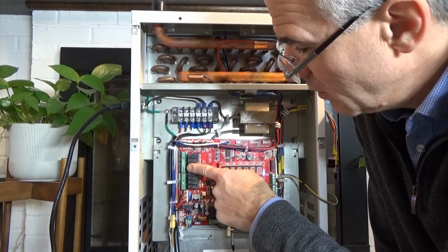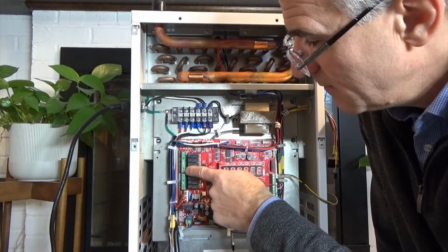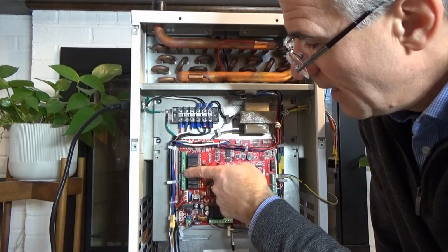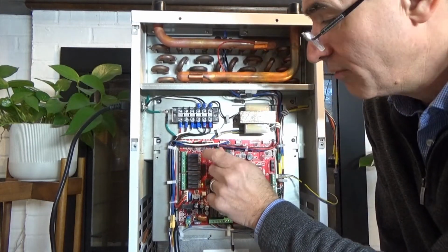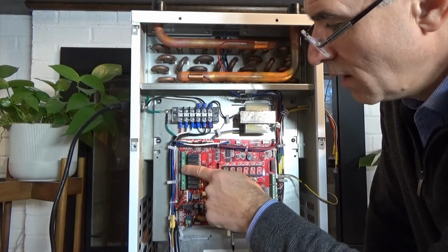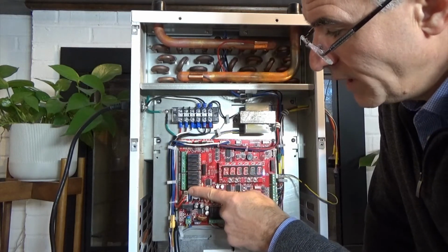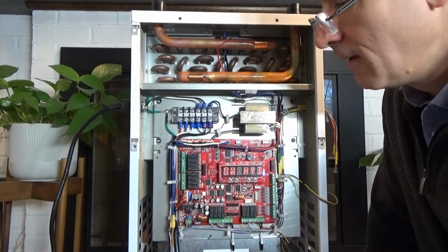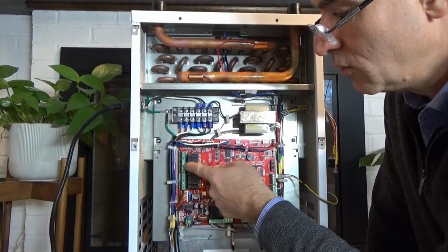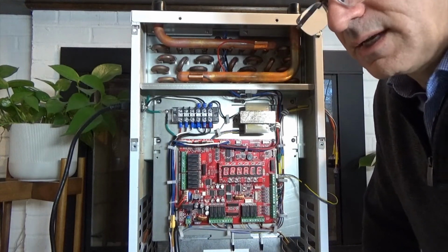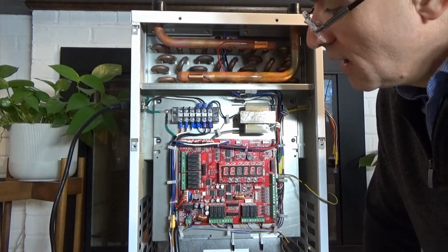Below the humidifier we have O, C, and B, or heating W1, C, and W2, but this is for your heat pump reversing valve. So when we're using a heat pump, we know that the Y1 will then be calling the compressor on, but depending on whether we're in heating or cooling mode as default, we'll need to send a signal out to the reversing valve to switch over.